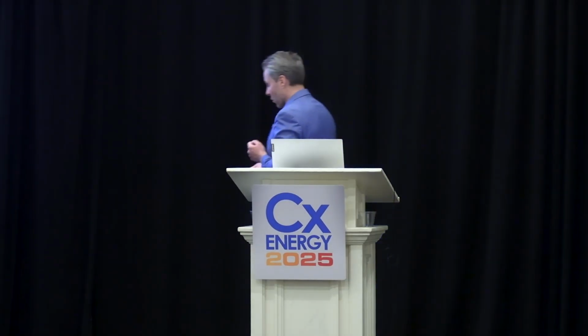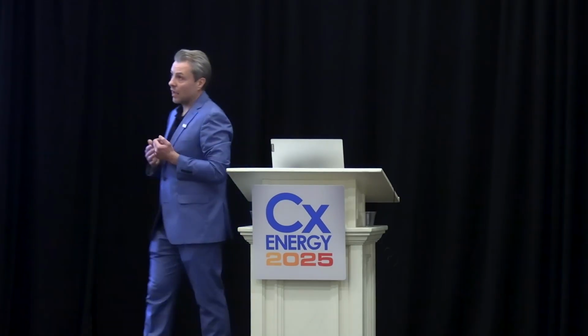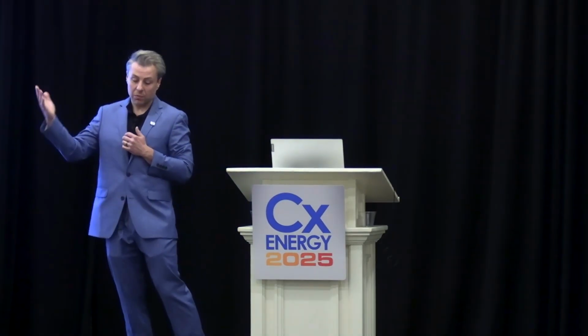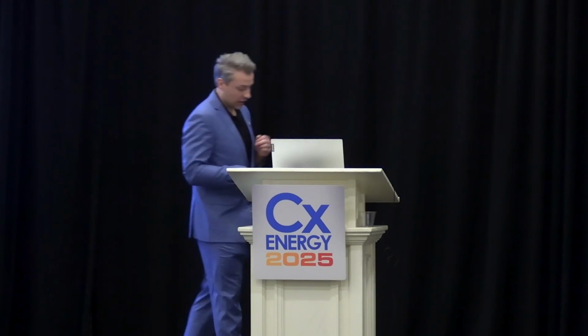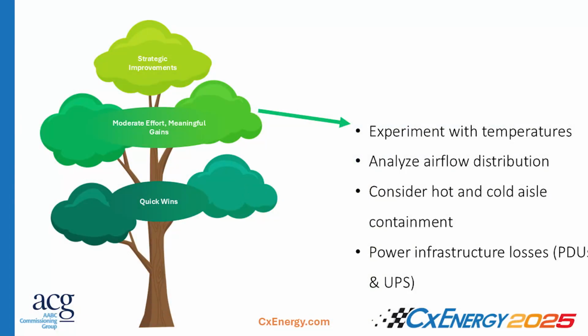The next two get more into a capital improvement project, but not quite a replace equipment capital improvement project. Hot aisle and cold aisle containment. This is not a new thing, but if you get into these data centers that were built in the 90s, like some of the ones that I worked in, they pretty much just threw the CRAC units wherever they thought they needed to go, put the racks near them, put the floor tiles where they thought they needed to go, let it rip. There was no thought to containing the cold air and the hot air and keeping them segregated.